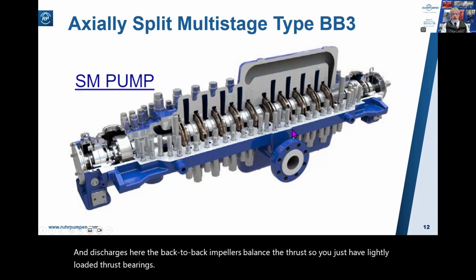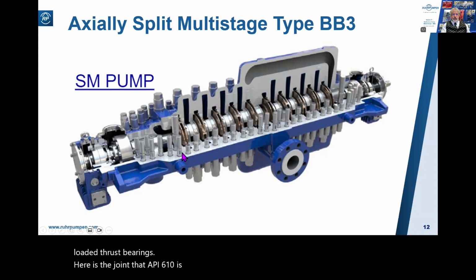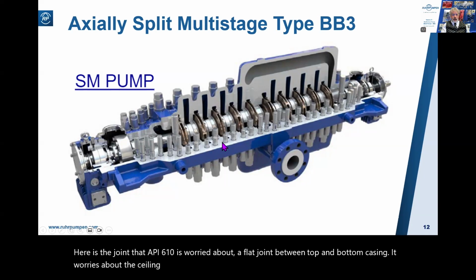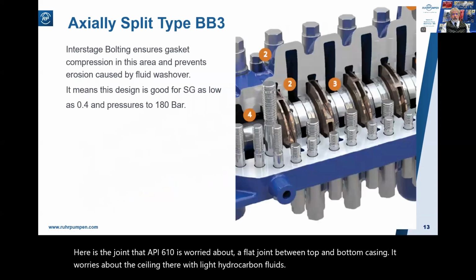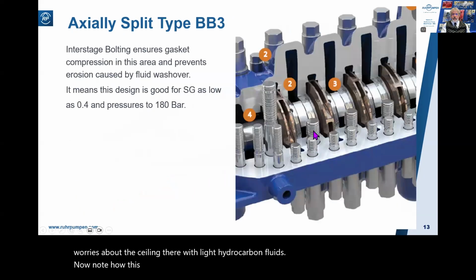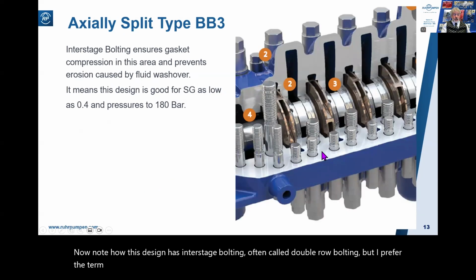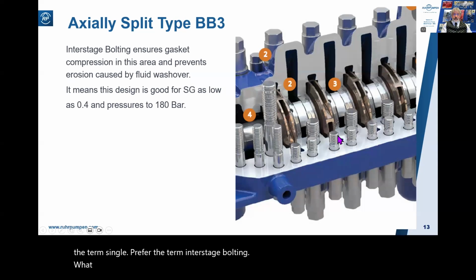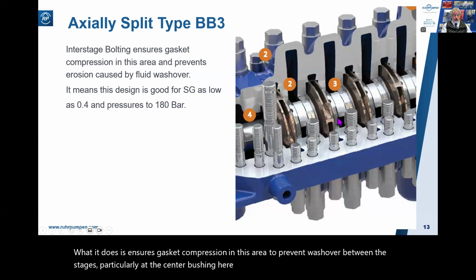Here is the joint that API 610 is worried about, the flat joint between top and bottom casing. It worries about the sealing there with light hydrocarbon fluids. Now, note how this design has interstage bolting, often called double row bolting, but I prefer the term interstage bolting. What it does is ensure gasket compression in this area to prevent washover between the stages, particularly at the center bushing here, where the delta P is at its greatest.